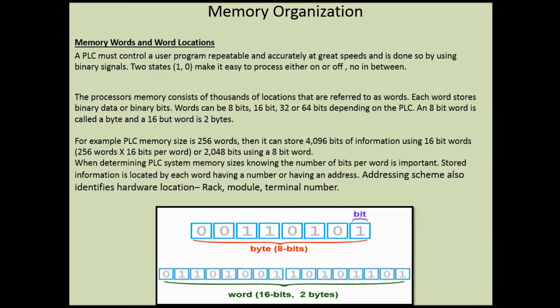An 8-bit word is called a byte and a 16-bit word is called two bytes. For example, if a PLC memory size is 256 words, it can store 4096 bits of information using a 16-bit word - that's 256 times 16 equals 4096. If it were only an 8-bit word, it would be 8 times 256 which gives you 2048 - half the capacity. So it's really important to figure out what size the bit words are so you know the actual capacity of your PLC.